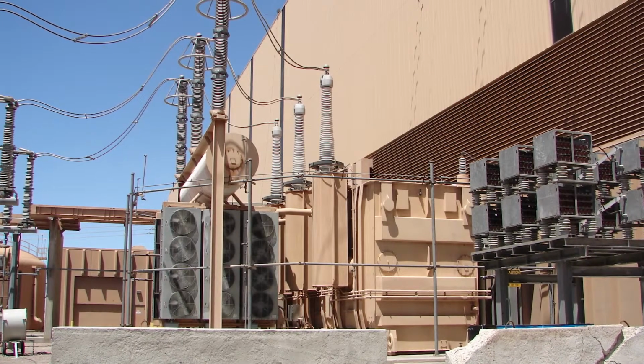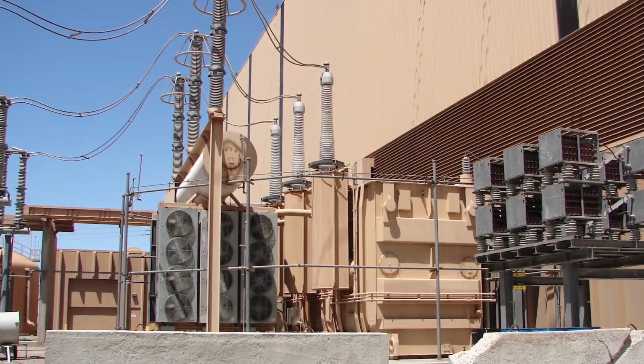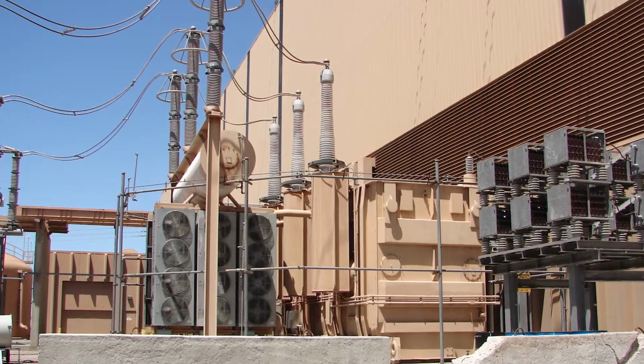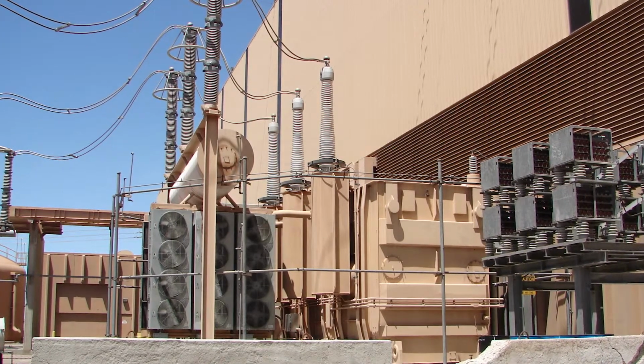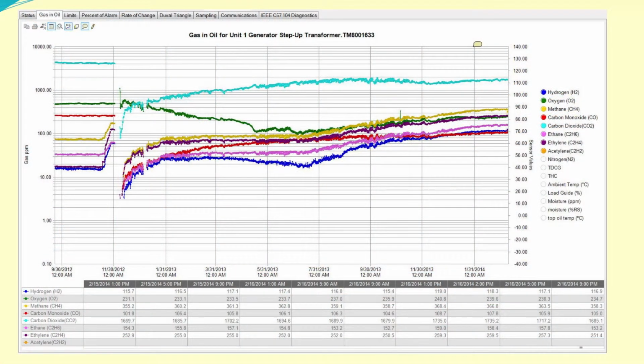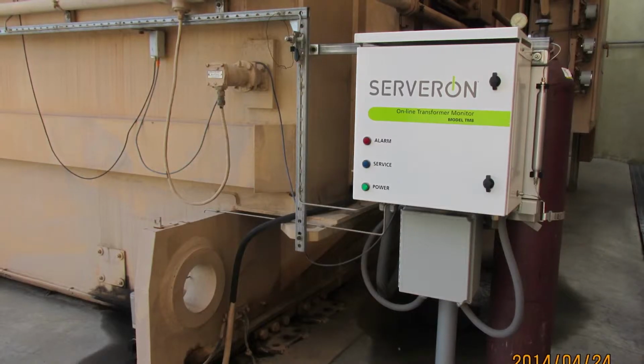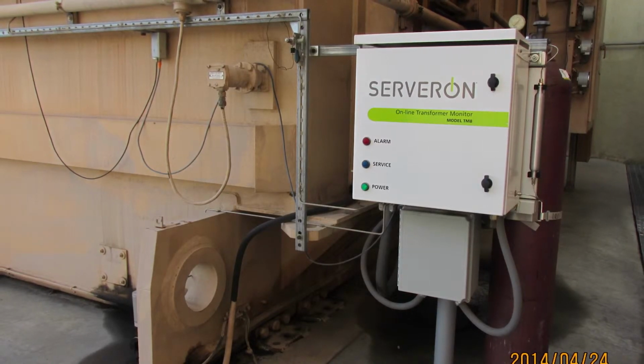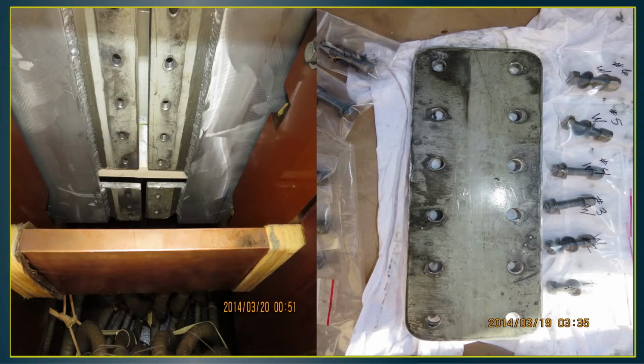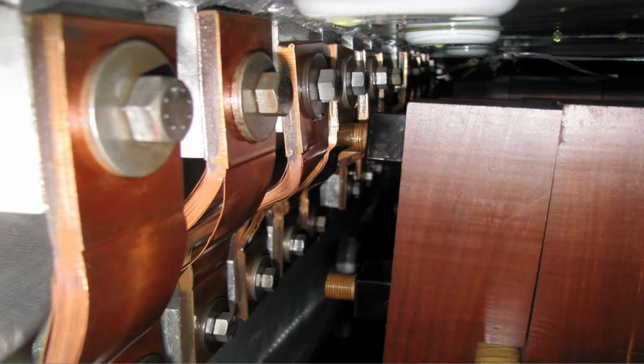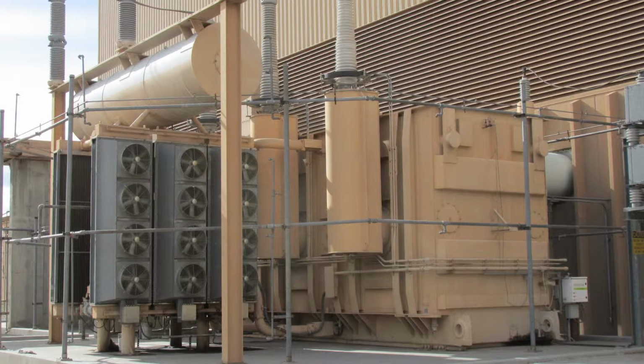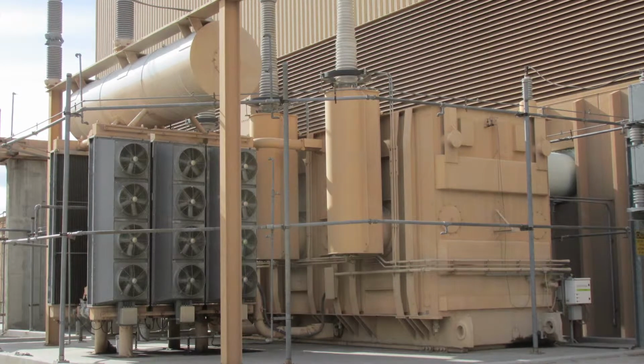Major maintenance was also conducted on Intermountain's Unit 1 transformers. The generator step-up transformer oil was drained and internal inspection done to locate a suspected arcing problem responsible for dissolved gases being detected by oil samples and the Serveron online gas analysis continuous monitoring system. A problem was found with the connections on the splice plates for the flux shield jumpers, flux shield supports, and the flexible copper straps. Replacement splice plates and new bolts were installed over this last weekend. 2 leaking current transducer penetrations were repaired.